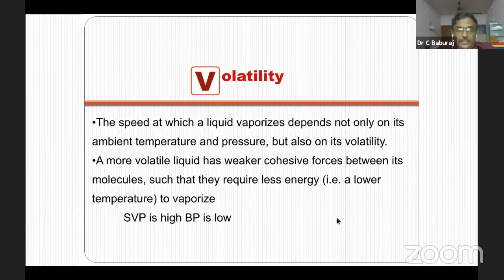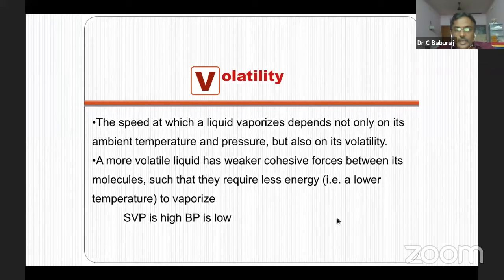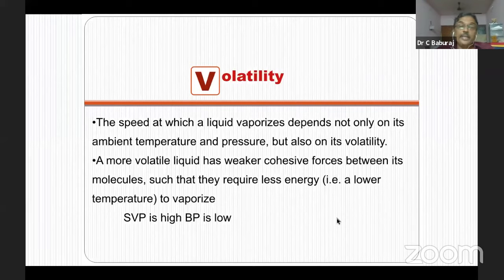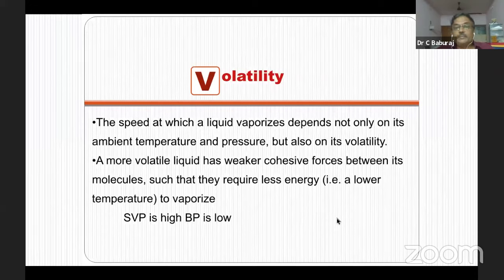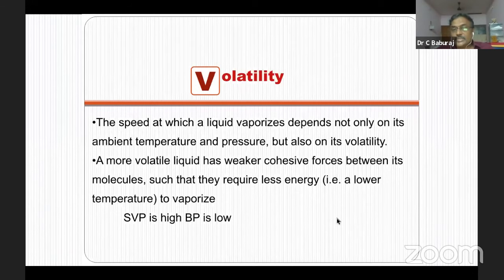The speed at which a liquid vaporizes depends not only on ambient temperature and pressure but also on its volatility. A more volatile liquid has weaker cohesive forces between its molecules, requiring less energy. For example, desflurane has a very high SVP of around 690 and its volatility is much higher than halothane whose SVP is around 248. Three factors determine the speed of vaporization: temperature, pressure, and volatility.